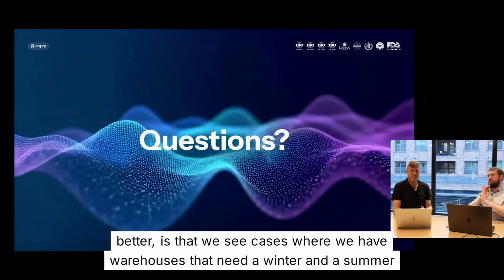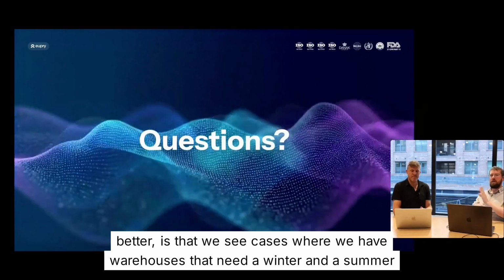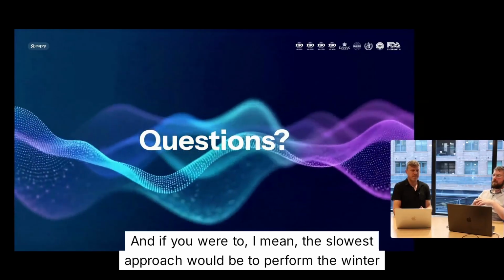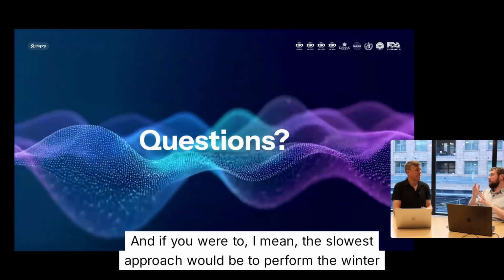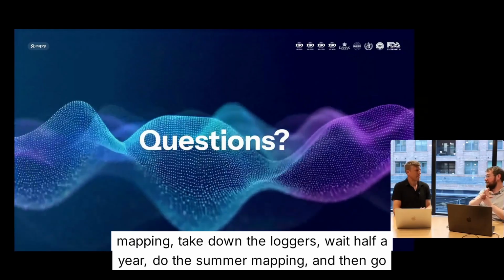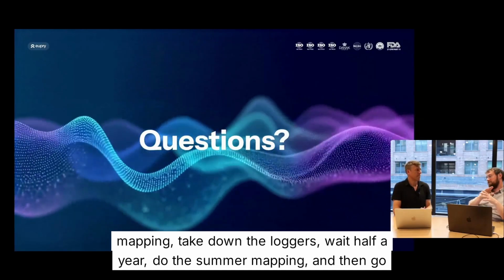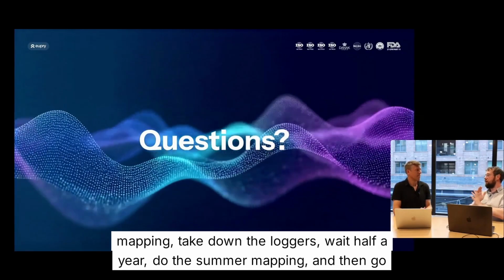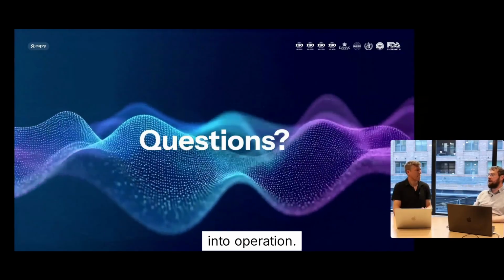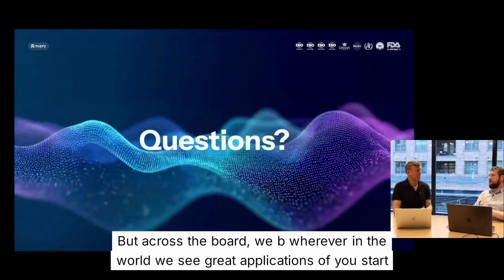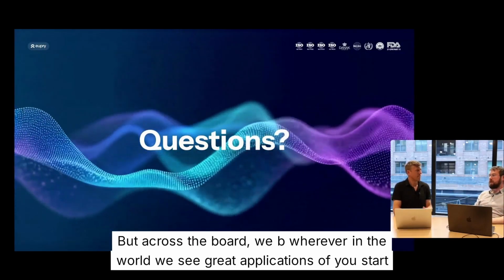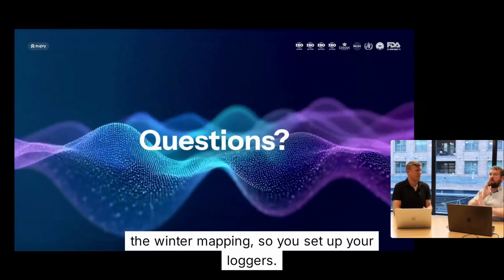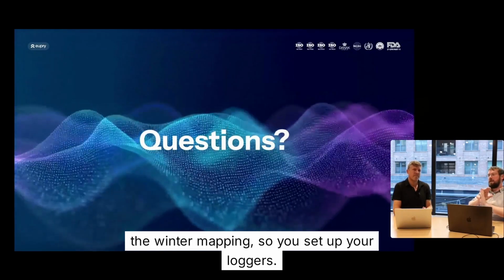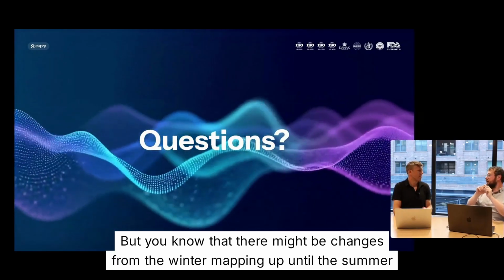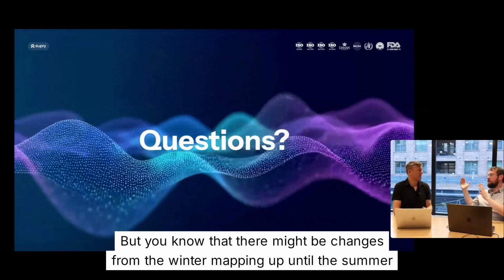But another approach where we see this, which might exemplify this a little bit better, is that we see cases where we have warehouses that need a winter and a summer mapping. And the slowest approach would be to perform the winter mapping, take down the loggers, wait half a year, do the summer mapping, and then go into operation. But across the board, wherever in the world, we see great applications of, you start the winter mapping, so you set up your loggers, but you know that there might be changes from the winter mapping up until the summer season.